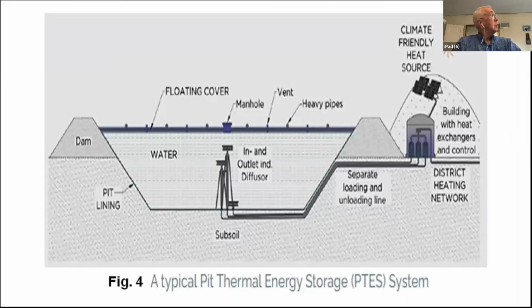Moving along now to something much different. Instead of boreholes in the ground, which we've been talking about, suppose we have a water pit. And it could be a natural lake as well. This is done quite a bit with ground source heat pumps. People put a heat exchanger at the bottom of a pond or a lake, and that works. You have pretty good stable temperature. But not everybody has a pond or a lake nearby that they can take advantage of that way.